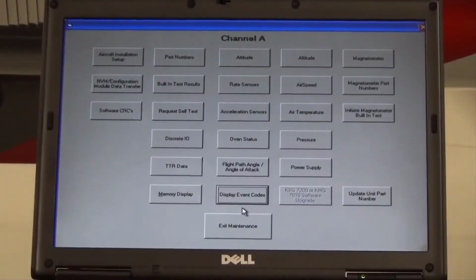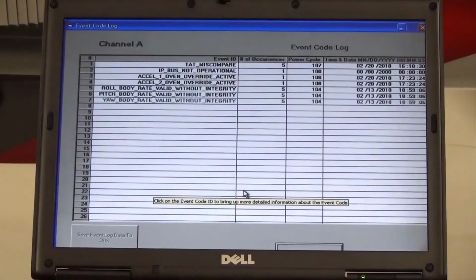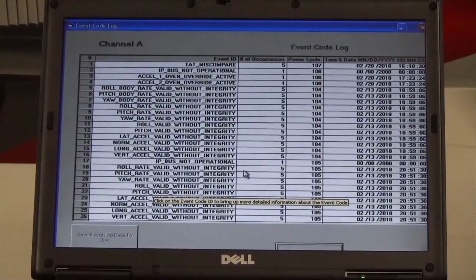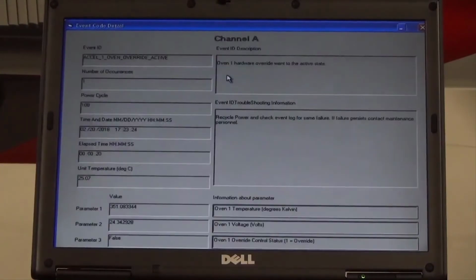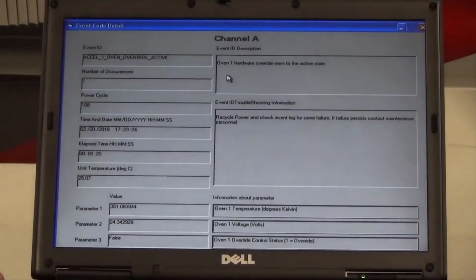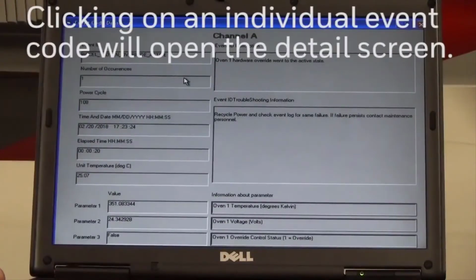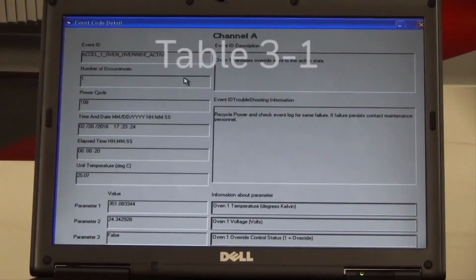For additional fault isolation, utilize the Display Event Codes button. The event code log will appear. Individual event codes can be selected. Once an individual event code is selected, utilize Table 3-1 in the KSG 7200 installation manual for fault isolation guidance, and/or send the event code.txt file to Honeywell Technical Support for additional assistance.